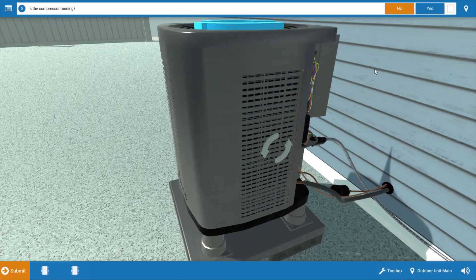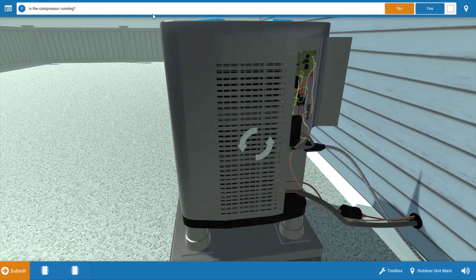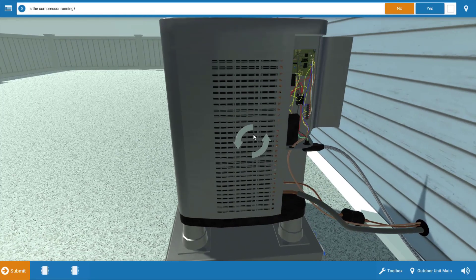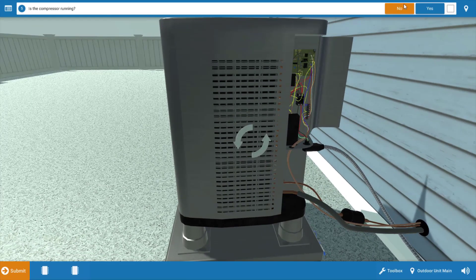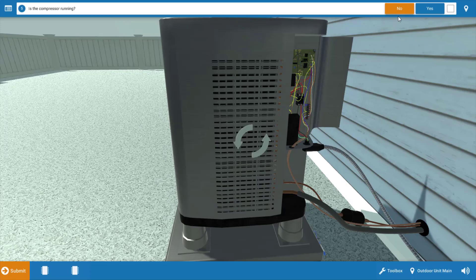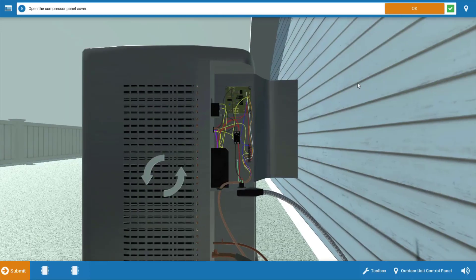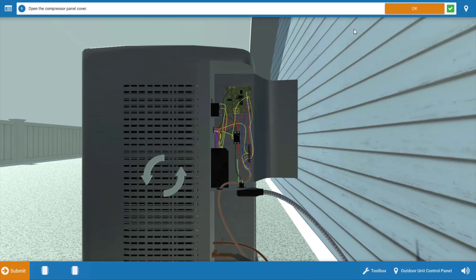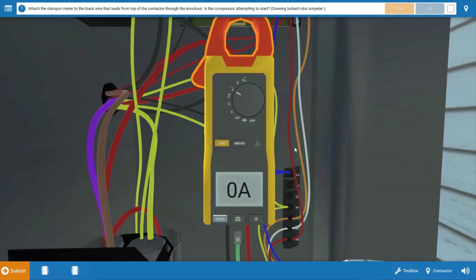Next, the compressor. Is the compressor running? Well, at first glance, it looks like the compressor is not running. So we're going to say no, but it's possible that the compressor is cycling on its internal overload. So we're going to open the compressor panel, which we've done, or the control panel. We're going to click OK.